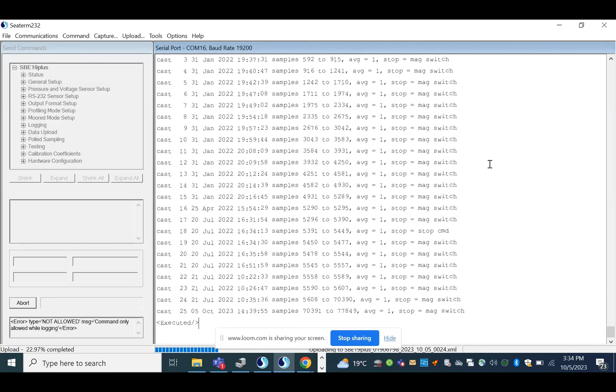Now that we have connected the SBE 19 plus V2 to our SeatermV2, we'll configure the 19 plus for profiling mode. It's important for you to enable all the auxiliary sensors you have connected to the 19 plus V2. Make sure that the pump is on. You can do that by ensuring that the minimum conductivity frequency is of the right value. So if you're deploying the instrument in salt water, it will be your zero conductivity frequency, which you can find in your calibration files, plus 500 hertz. And in fresh water, you will add 50 to the zero conductivity frequency.